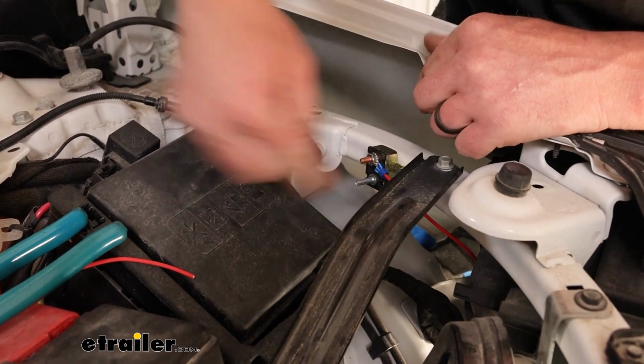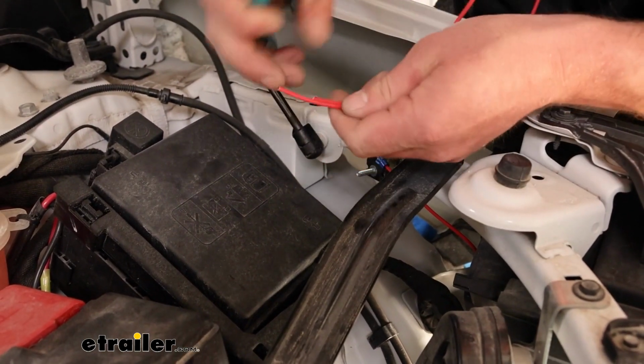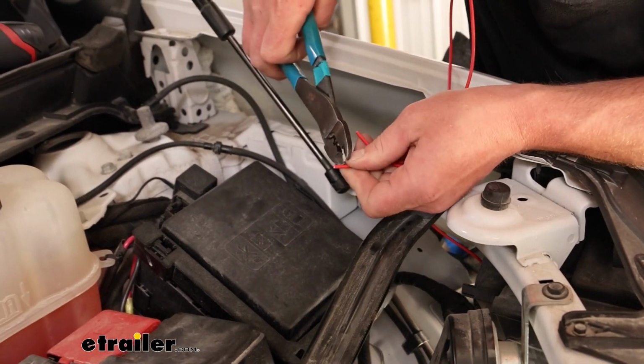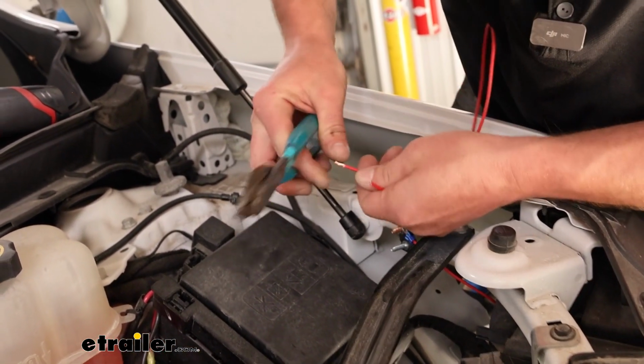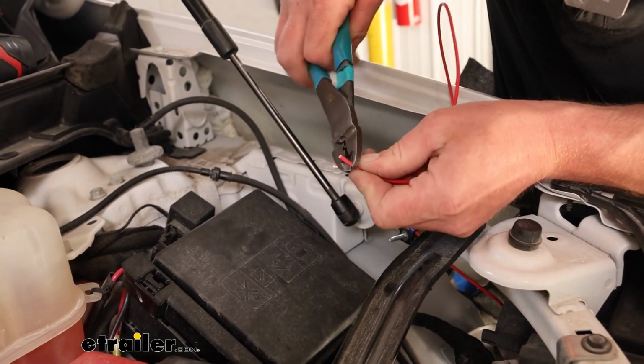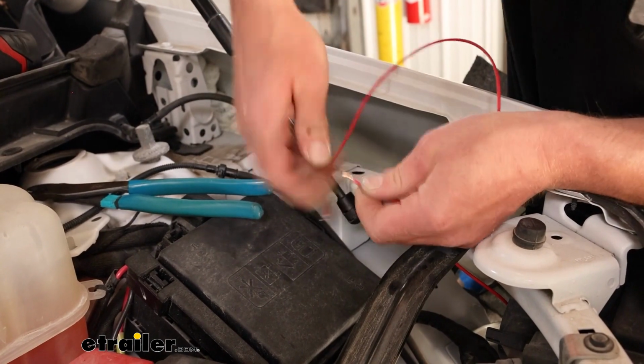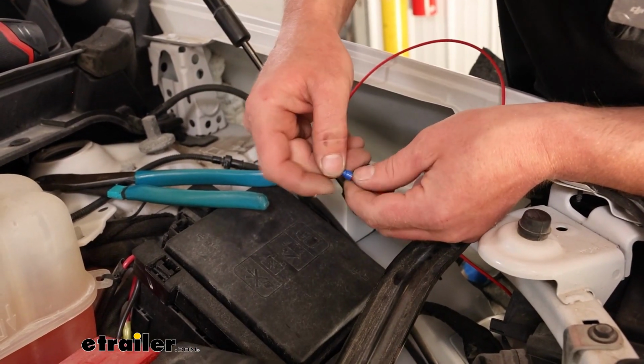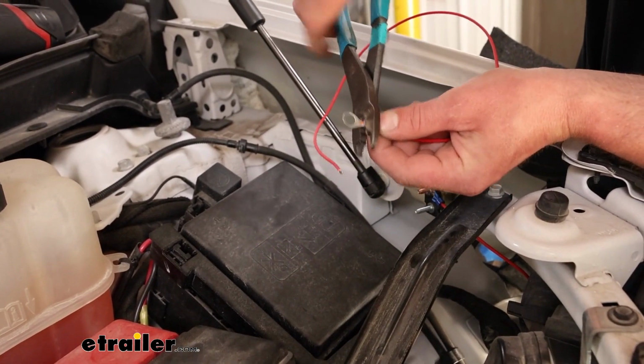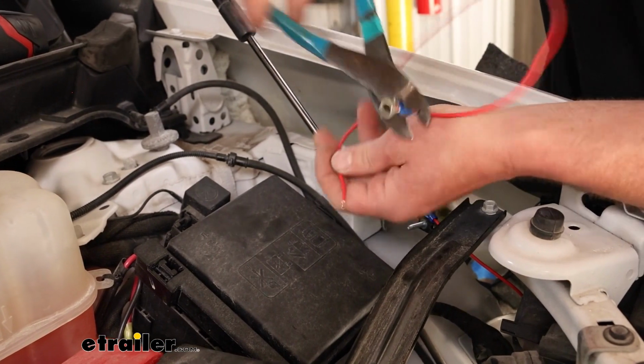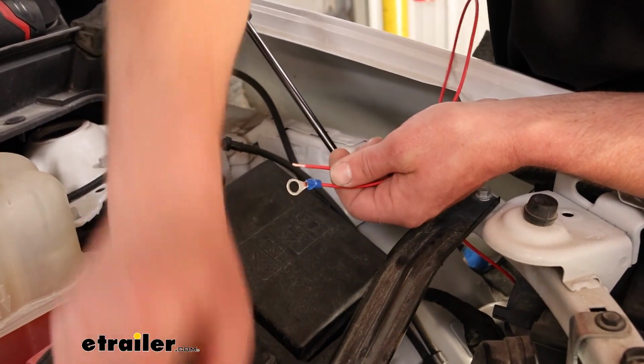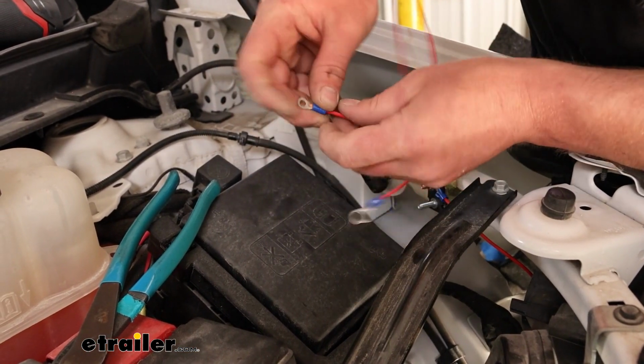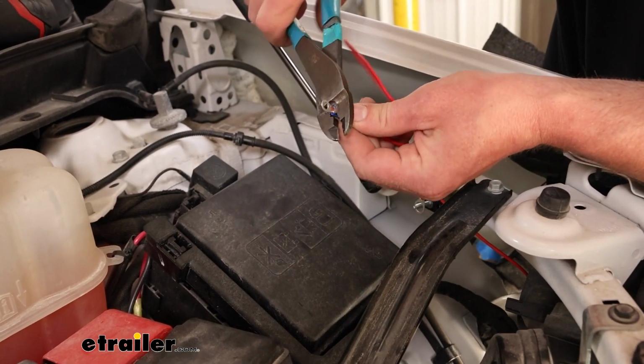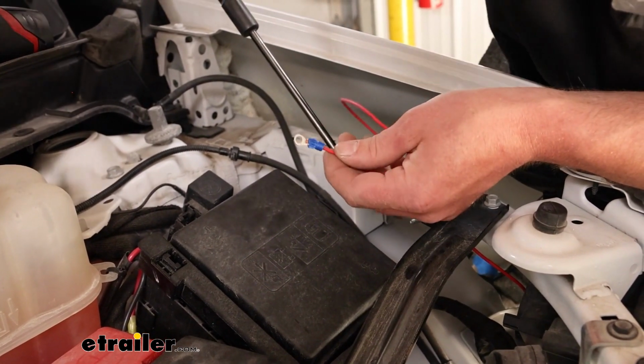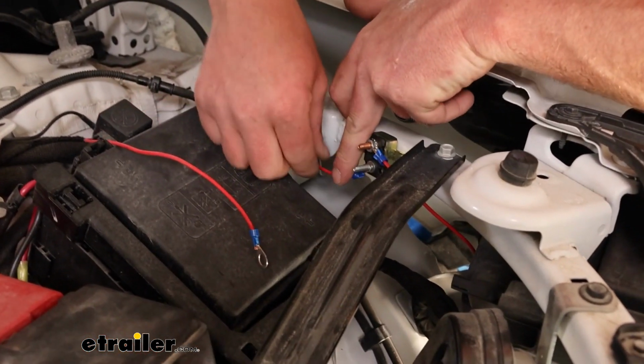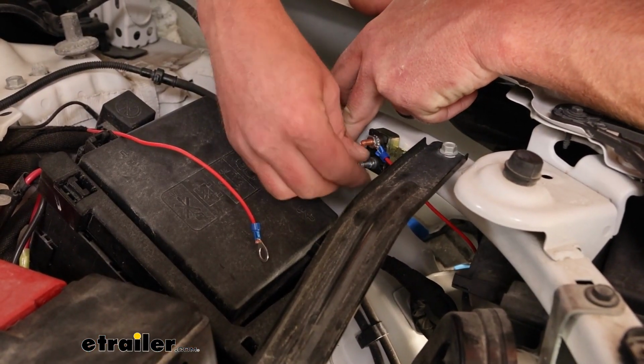And then for this post here, we're going to take the remaining portion of the wiring. We'll strip both ends back, and one of them we'll put on a larger ring terminal, and a smaller ring terminal on the other end. We'll set this up on our breaker here. The small end will go over the silver post, and I'll get this tightened down.